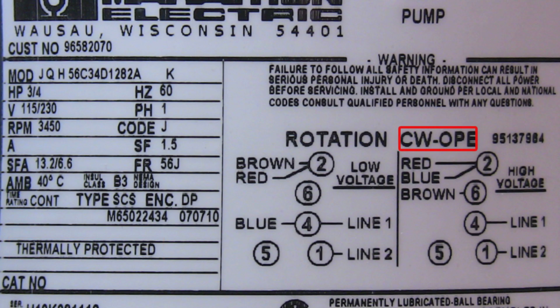CW indicates the motor spins in a clockwise direction, while CCW is counterclockwise. Although it is possible to change the rotation on some motors, this only applies to larger 3-phase motors and 1-phase motors where directions are listed. This motor only spins clockwise.